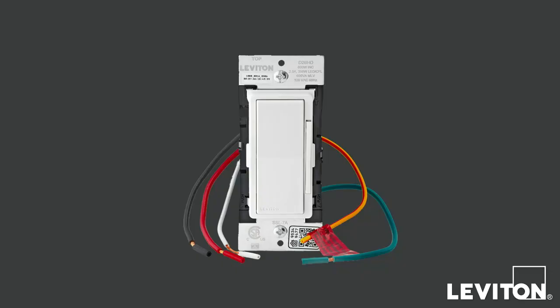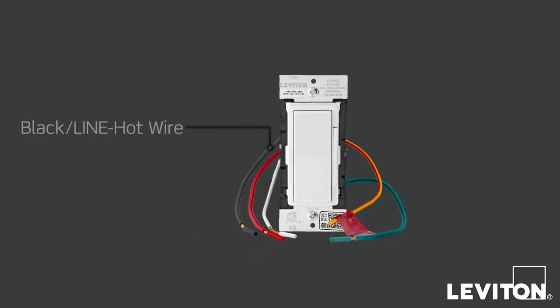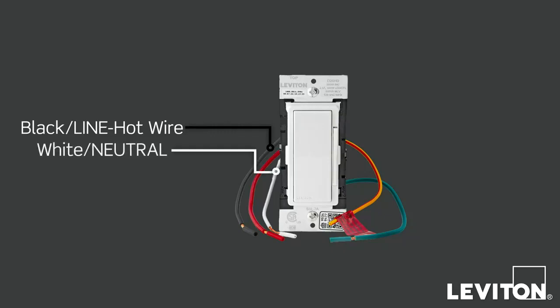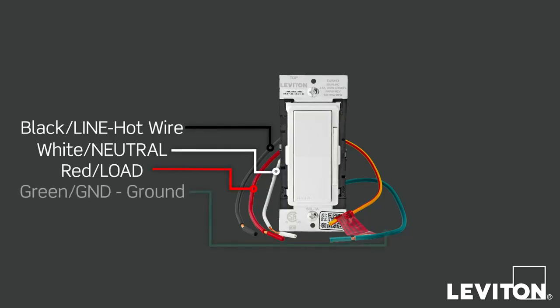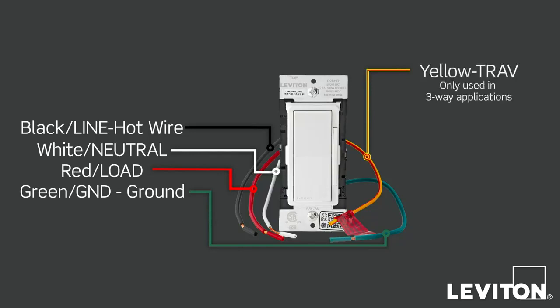Before installing, it's important to identify the wires on your switch or dimmer to ensure that you're wiring correctly. The Decora Smart Wi-Fi 2nd Generation wallbox devices use wire leads to make installation easier. Black is for the line or hot wire. The white is for the neutral wire. The red wire is for the load connection. And the green wire is for the ground connection.